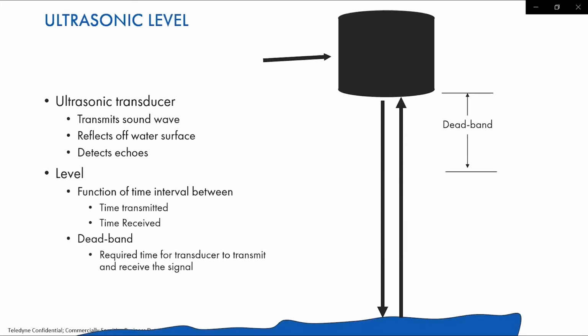Other things to remember is ultrasonic sensors use a temperature sensor internally, and the purpose of that is to calculate the speed of sound. Why that's important is that if you have your ultrasonic sensor in direct sunlight, the sensor could be, and will be, hotter than the ambient air temperature, so it doesn't calculate the speed of sound correctly. It expects that return signal to come back sooner. Then when it picks up that signal a little bit later, you end up finding that your levels become a little bit lower because it doesn't compensate for the temperature. So in that case, you want to make sure you have a sunshade or something over the top of that sensor so it isn't in direct sunlight.